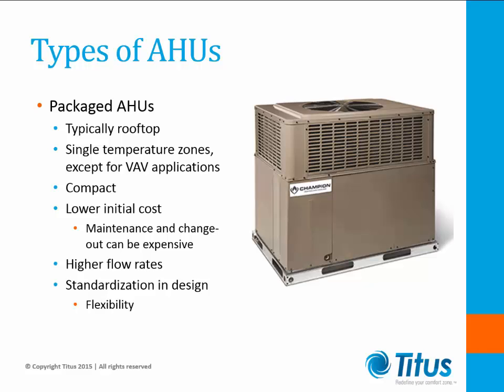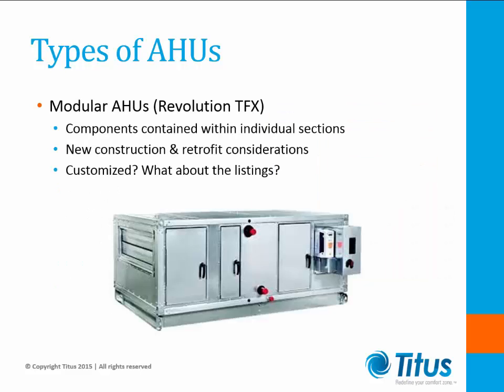Packaged units have flow rates from a few thousand CFM to as much as 30,000 CFM. The units tend to be standardized in design, thus limiting the flexible nature of offering an array of sizes to meet expansion opportunities. A third type of AHU would be a modular construction. This modular construction can be identified to the Revolution TFX. Modular AHUs offer flexibility to be more selective in components and sizes. Modules are assembled at the factory or can be shipped individually and assembled on site. They are capable of being segmented or broken down to fit in elevators or through smaller door openings. They are great opportunities for retrofit applications. Many times these units are considered semi-custom units, which carry certified listings over the other custom units in the field.